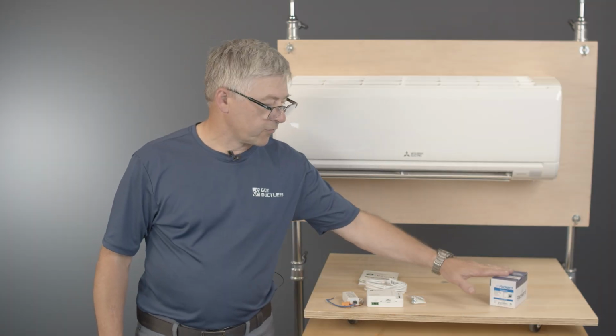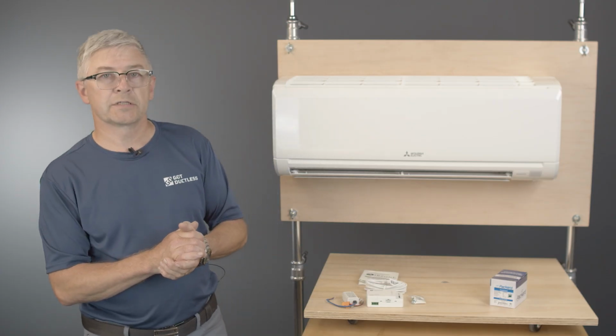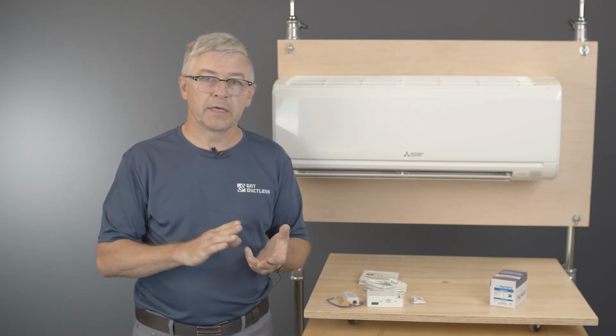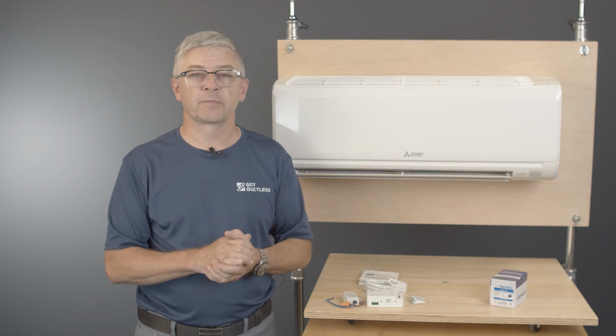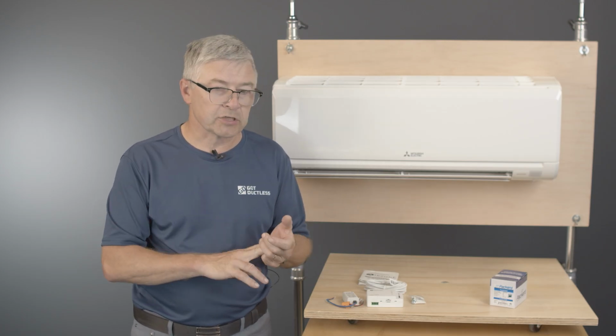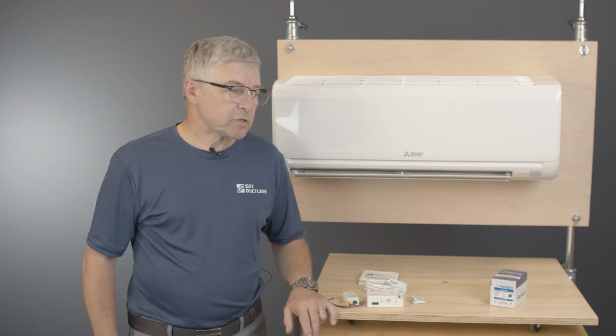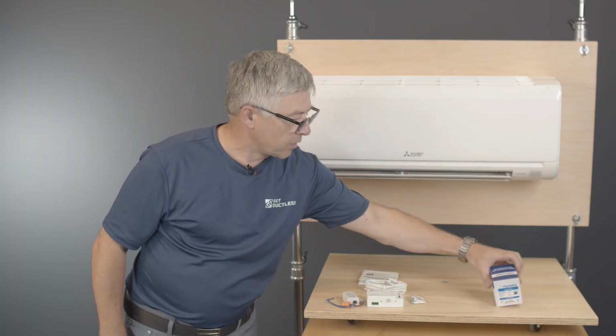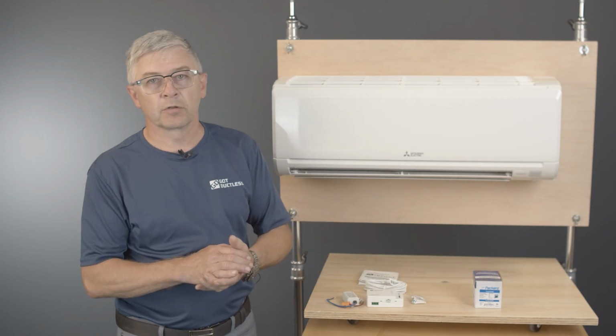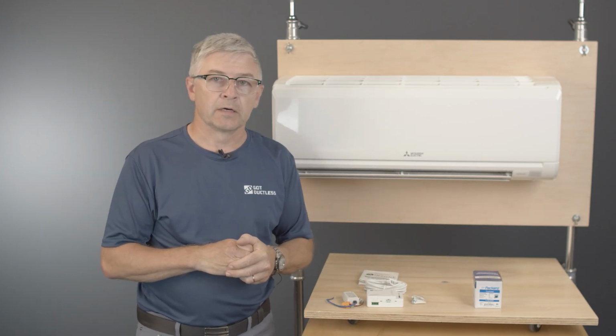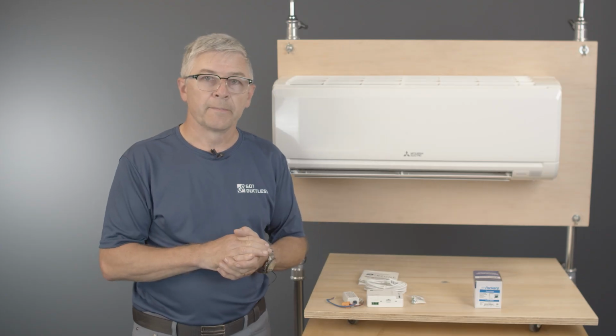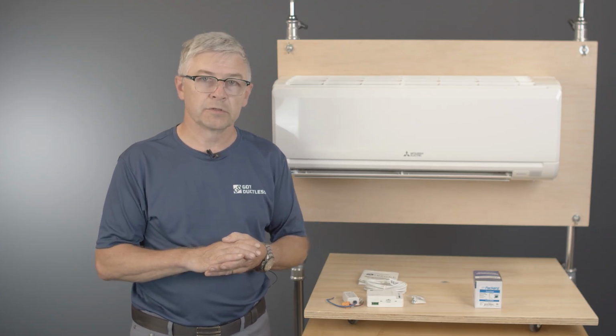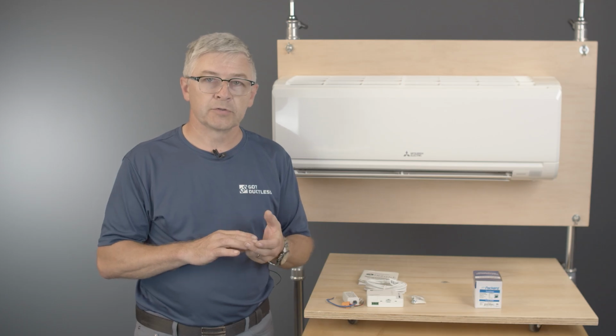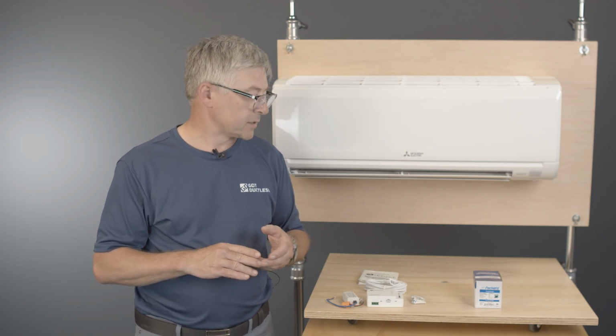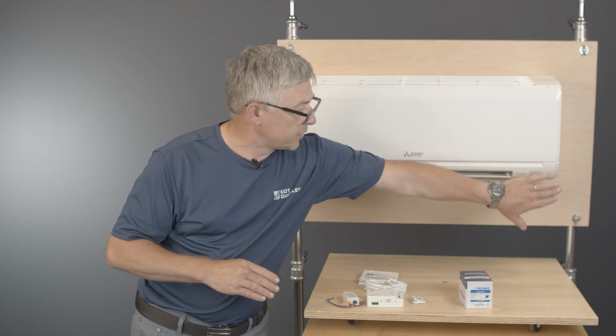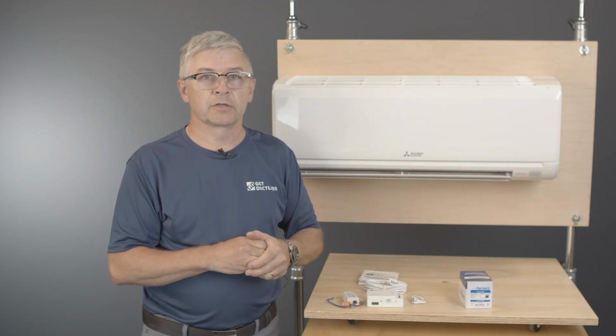Besides this 24-volt transformer, you need a couple of other accessories, such as thermostat wire—could be 18/8 or 18/5 depending on what kind of thermostat you have—and maybe an electrical junction box and access panel. Mitsubishi doesn't have any dedicated place for this transformer, so your installer has to be somewhat creative to hide it somewhere in the wall and make sure it's installed to electrical codes. We always recommend using electrical junction boxes, installing it somewhere around the unit, and covering it with an electrical access panel.